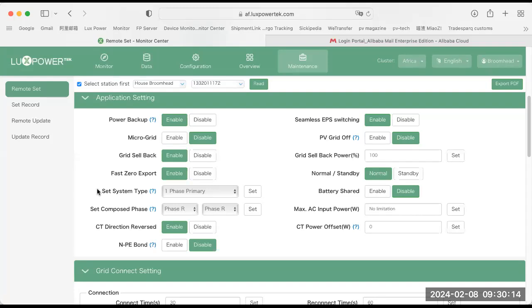All right, so if you have a look underneath here, you will also have the communication terminals, or what we call the interface board. So you have your battery communication there. It's got a dual row of dip switches. The top is for your country or the region that you're in, and we typically don't change that because you can do the settings on the machine. And then the bottom one, as you guys know, we used to have a red dip and a blue dip. So the new LXP5s come with a blue dip, which means we've changed the CAN communication from 3 and 4, and it's now 4 and 5 for CAN low and CAN high.